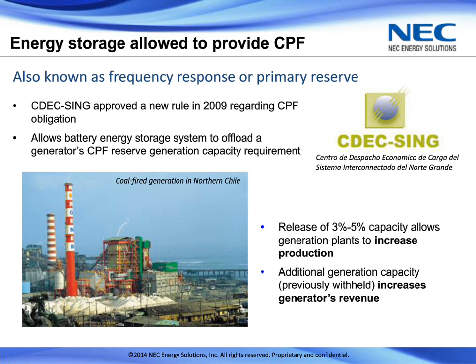So instead of, let's say, a coal-fired generator, which you can see in the picture there, reserving their capacity on the order of 3 to 5%, they could take that obligation and have it be met by an energy storage system instead. So what does this do? It allows that generator to then increase production by increasing their output of energy, and in that way increasing their revenue. So in other words, letting the generator do what it's good at, which is generating energy at the maximum efficient rate possible, and then allowing that obligation for CPF, or primary reserve, otherwise known as frequency response here in the States, to be provided by a battery energy storage system. So let the battery system do what it's good at, which is fast response, fast ramping, and fast compensation for frequency disturbances.